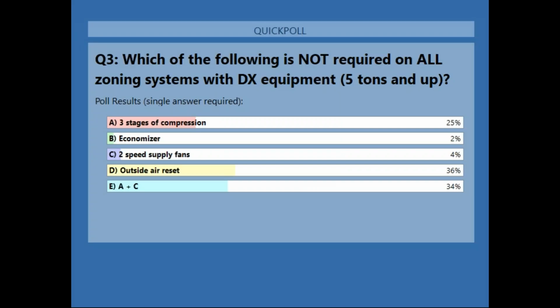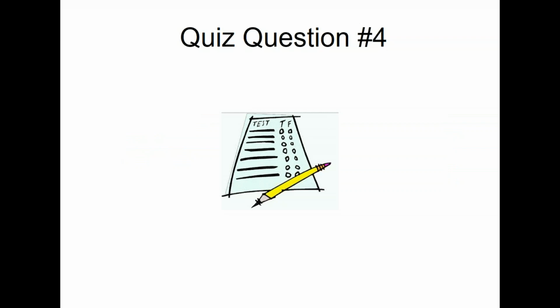All right, so most of you got the answer correct. I should say most of you. The highest correct answer was outside air reset. That is not required by code. If you have a zoning system for that size and up, 3 stages of compression is required, an economizer is required, a 2-speed fan is required. Outside air reset is not required. So not as many people got that right as I thought should have. So obviously I worded it in a confusing way, even though I stressed the not and the all. All right, keep on moving here.